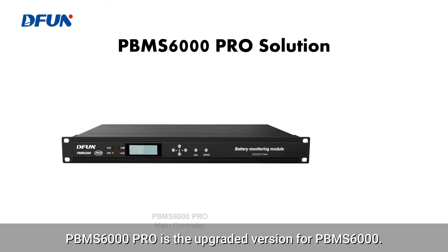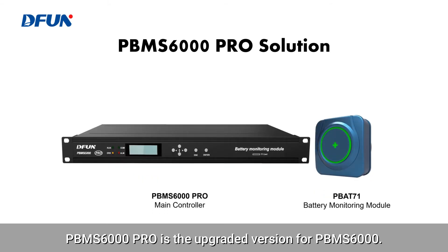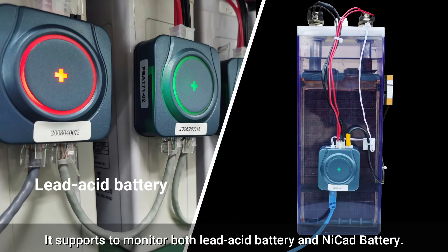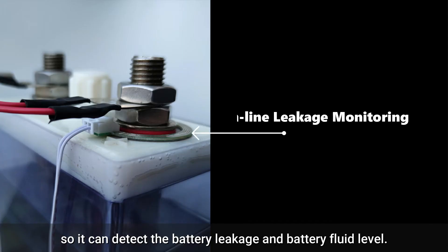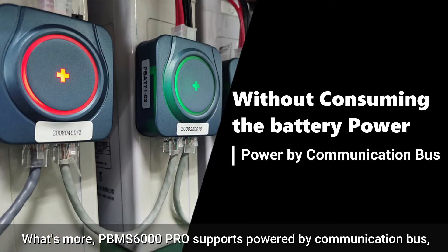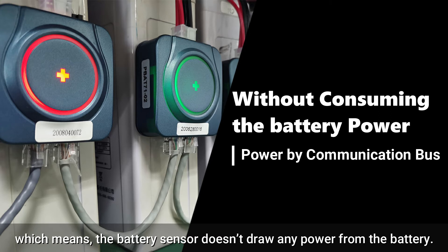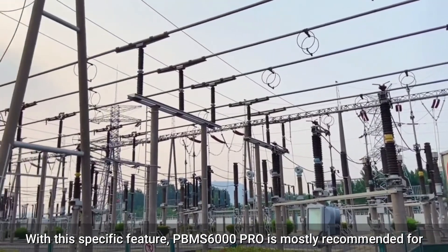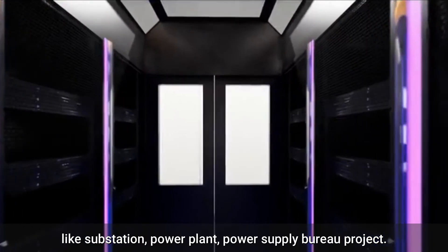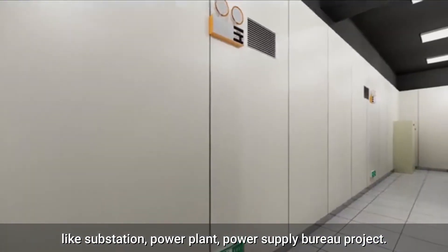The PBMS6000 PRO is the upgrade version of the P-BMS-6000. More functions have been added on the basis of P-BMS-6000. It supports monitoring both lead-acid batteries and nickel-cadmium batteries, so it can detect battery leakage and battery fluid level. What's more, the PBMS6000 PRO supports being powered by the communication bus, which means the battery sensor doesn't draw any power from the battery. With this specific feature, the PBMS6000 PRO is mostly recommended for the electrical power industry, such as substations, power plants, power supply bureau projects.